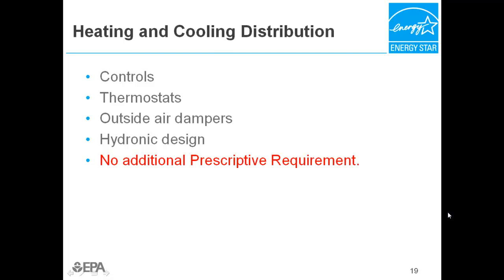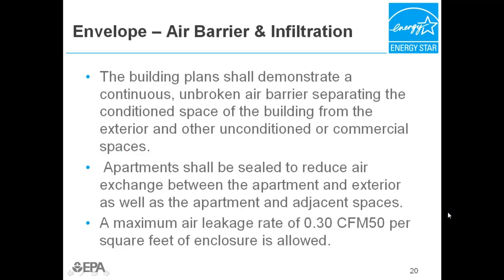The remaining prescriptive requirements related to heating and cooling distribution, controls, thermostats, outside air dampers, and hydronic design are all the same as the prerequisites in the performance path, and details can be found in the prescriptive path document. Also identical to the prerequisites in the performance path, buildings following the prescriptive path must demonstrate a continuous, unbroken air barrier, and apartments must be tested for air leakage, which cannot exceed 0.30 CFM50 per square feet of enclosure. As a reminder, the enclosure includes all surfaces: floor, ceiling, party walls, and exterior walls.